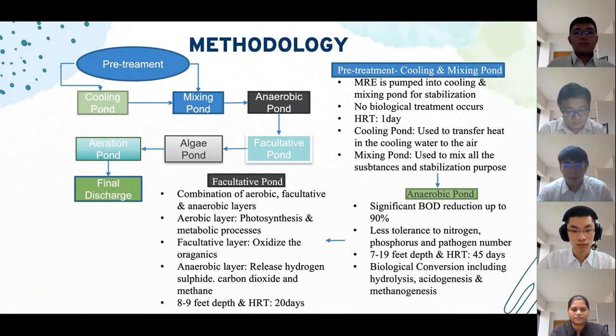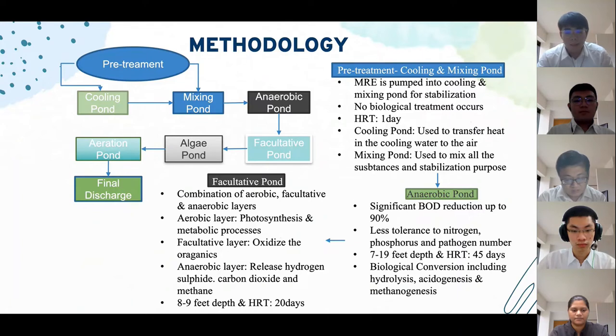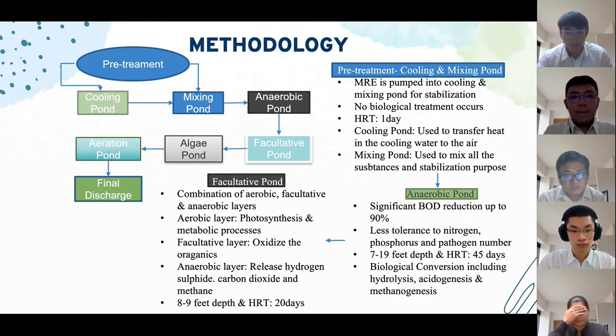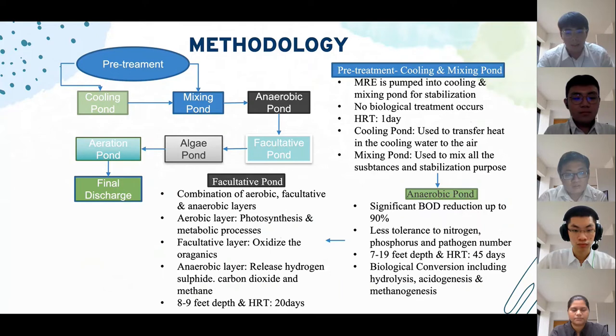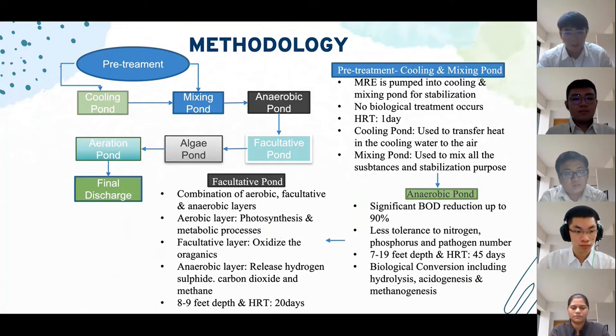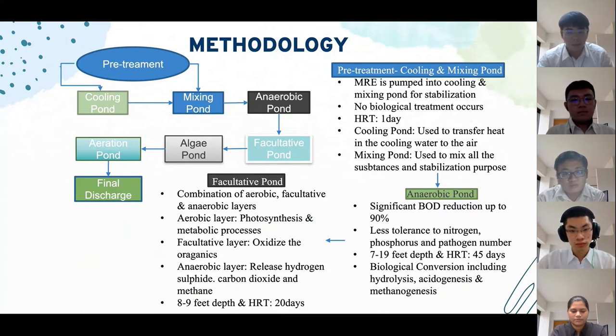Thank you, Yongjie. I am going to explain in detail how the ponding system works. The ponding system comprises pre-treatment as well as primary treatment. POME will be disposed into the cooling pond, followed by mixing, anaerobic, facultative, algae, and aeration ponds, and then finally discharged. For the pre-treatment, the mixed-raw effluent, known as MRE, is pumped into the cooling and mixing ponds for stabilisation. There is no biological treatment occurring in these ponds. HRT for cooling and mixing ponds is one day. The cooling pond transfers heat to the air, while the mixing pond mixes all substances for stabilisation.